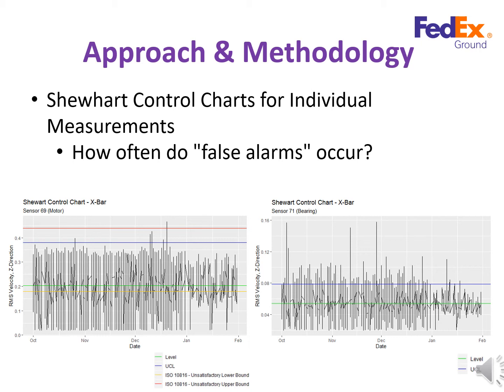For motor sensors specifically, lines representing ISO standard 10816 were also included. Using these charts, we calculated the probability that each sensor would obtain an out-of-control reading. Because there were no reported failures during the time in which this data set covers, these points are false alarms. They do not represent a true shift in the mean, but are a result of random variation.